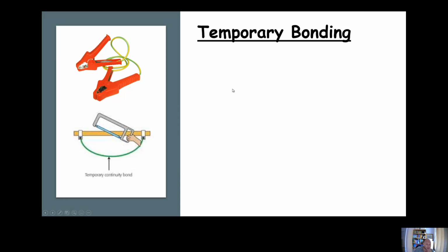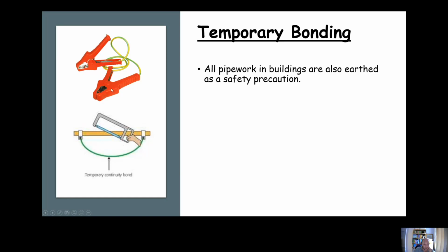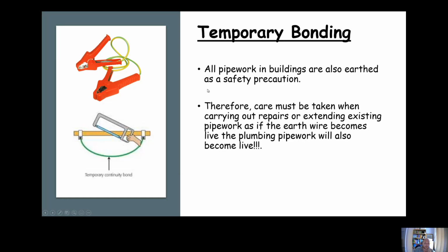Okay, temporary bonding. Here we have an example of temporary bonding, and we should use these whenever we cut into pipework. The reason for this is because the pipework might be live, and as long as there's a circuit, essentially the pipe is whole, the electricity will flow through the pipe and out through the earth wires, the main earth terminal, which we'll look at in the next module.